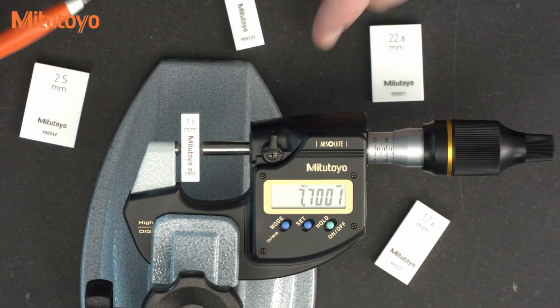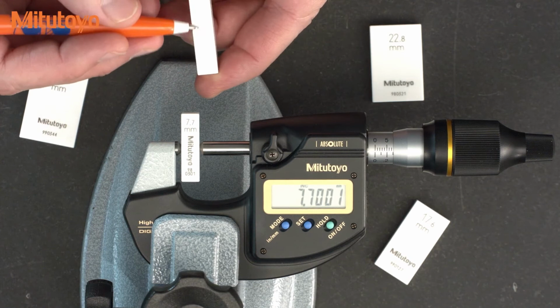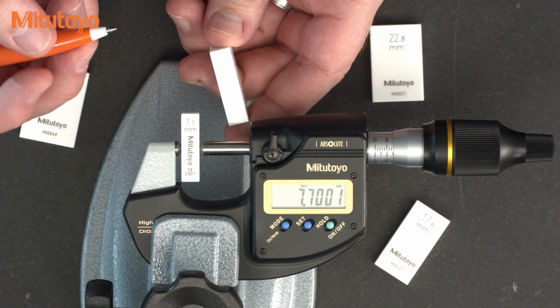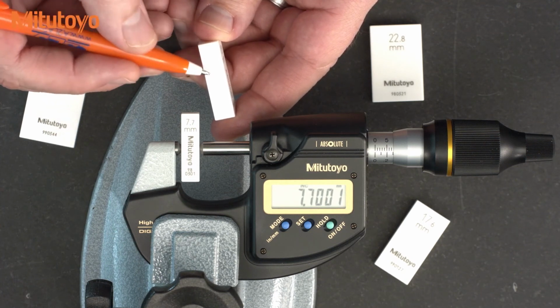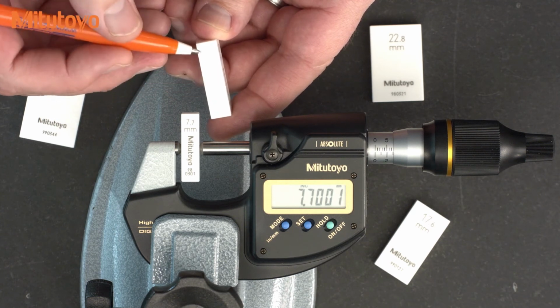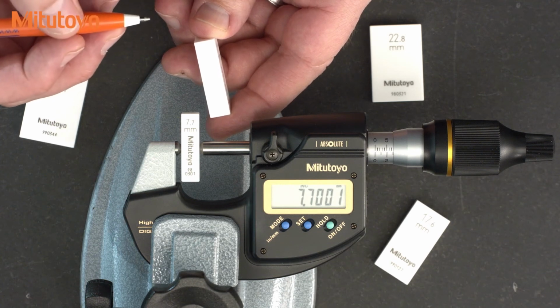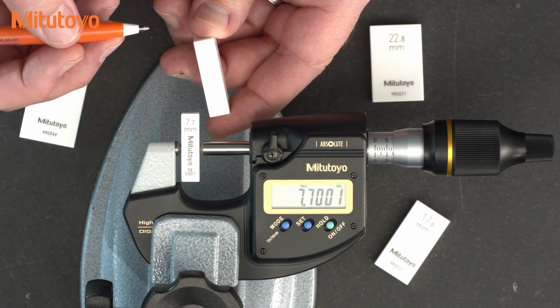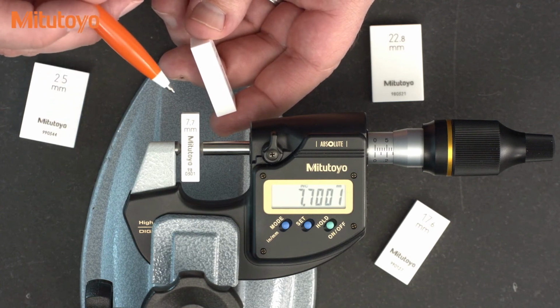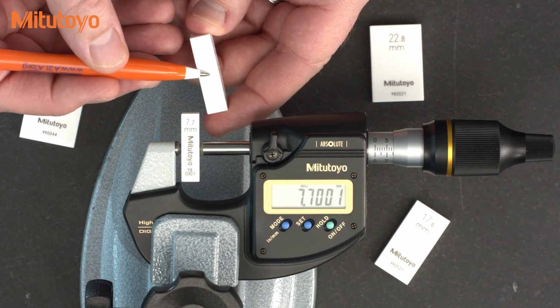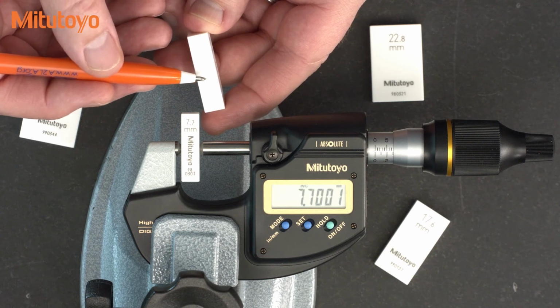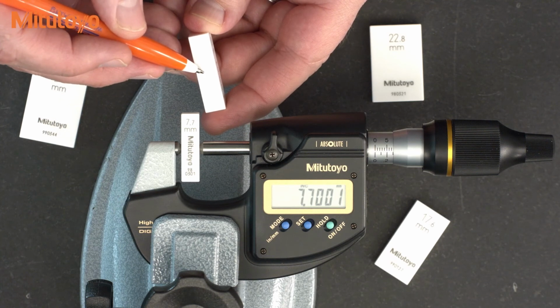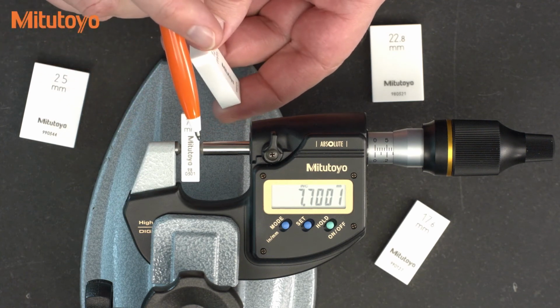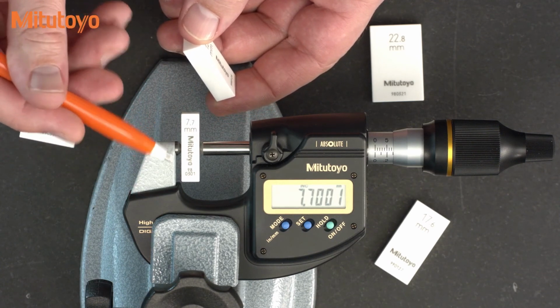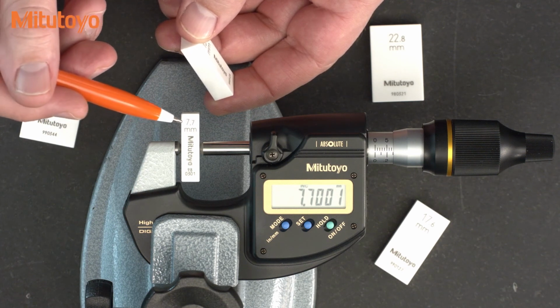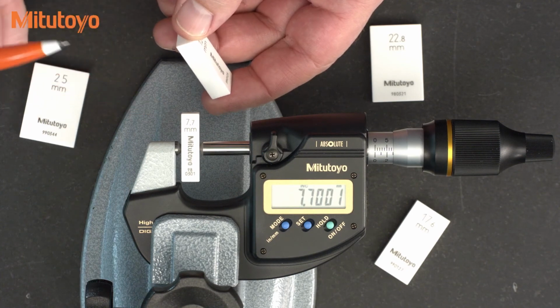Now, gauge block tolerances apply across the entire surface of the gauge block. When they are calibrated, if that's done correctly, the length is checked at multiple points, usually in the center and in all the corners. And all of those points must be in tolerance. Now, for that reason, grade 00 gauge blocks are challenging to manufacture and can be quite expensive. But what we noticed is that if we look at the center point alone, our grade 0 gauge blocks actually met the tolerance for the grade 00 gauge blocks at this point. So if we measure with these smaller measuring faces on the MDH 25 at only the center point, as you can see here, we can use the gauge block nominal value just like when calibrating any other micrometer.